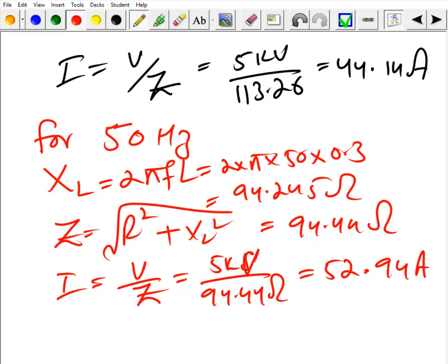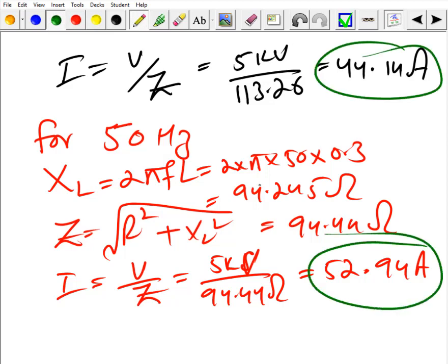Now with this very simple basic relation, we can understand what happens if the transformer is designed for 60 Hertz and if we try to operate it on 50 Hertz. We can clearly see that the current has increased by approximately 8 amperes.